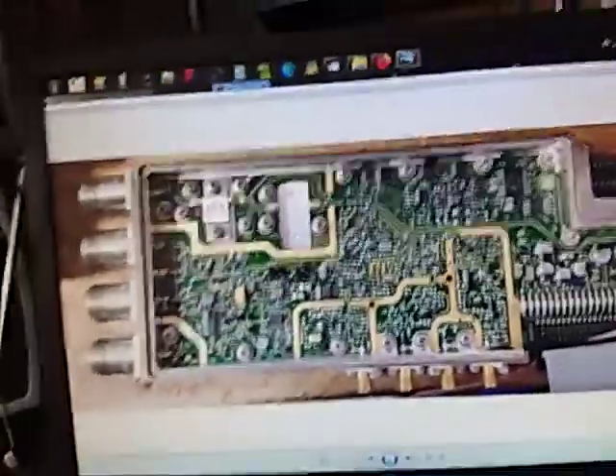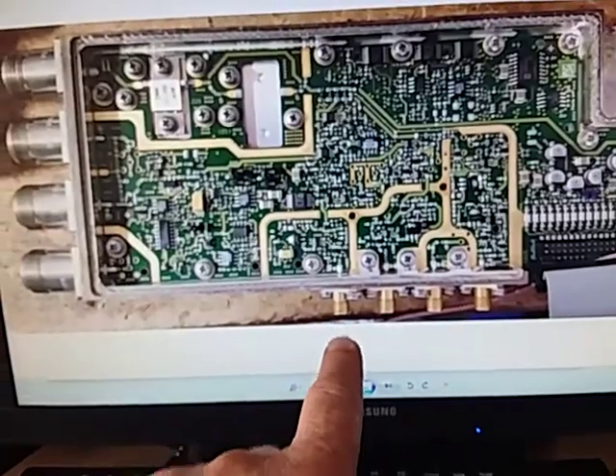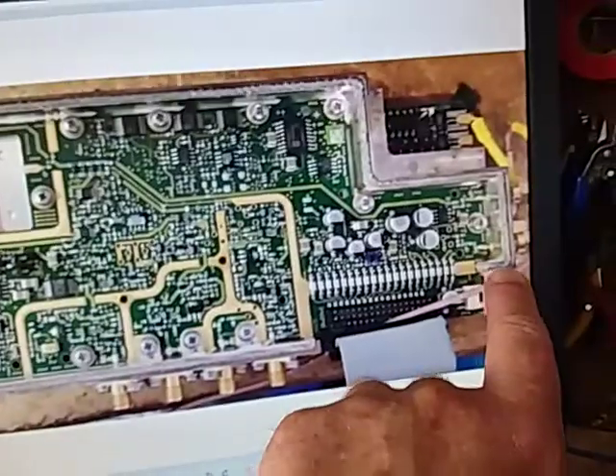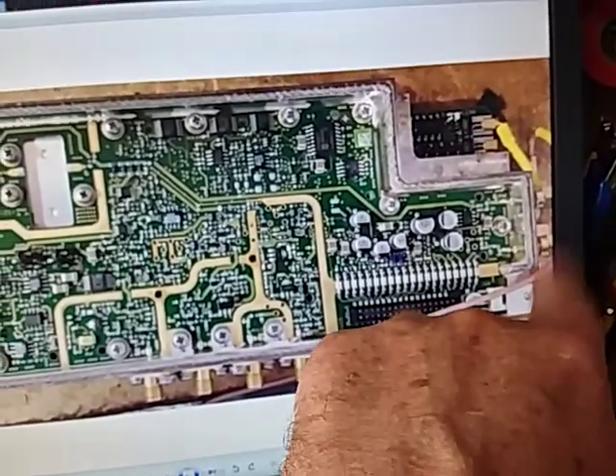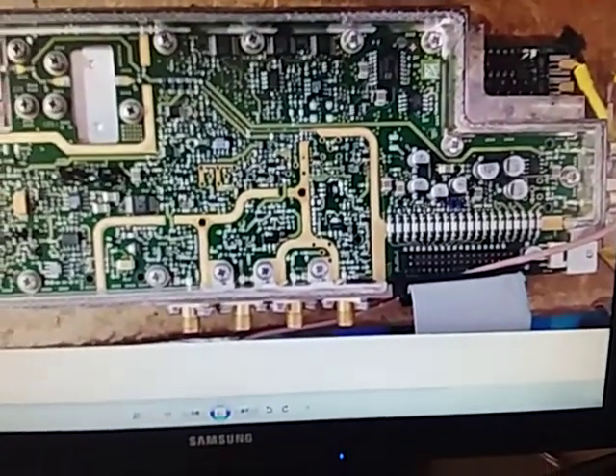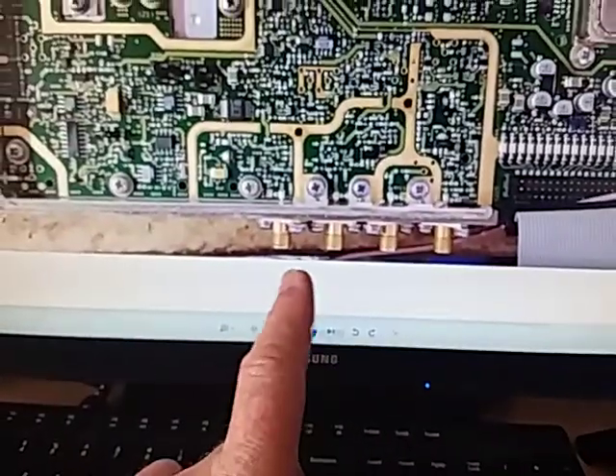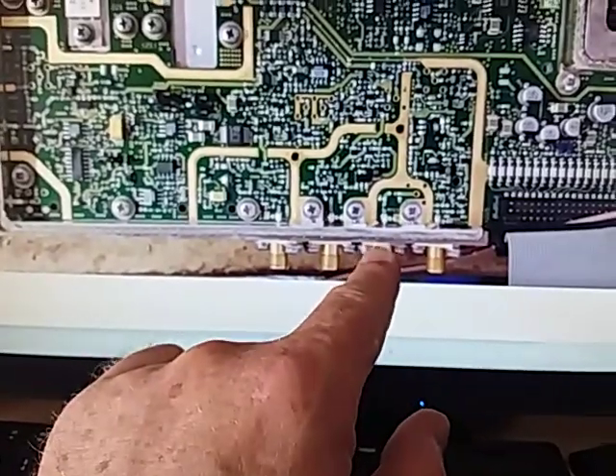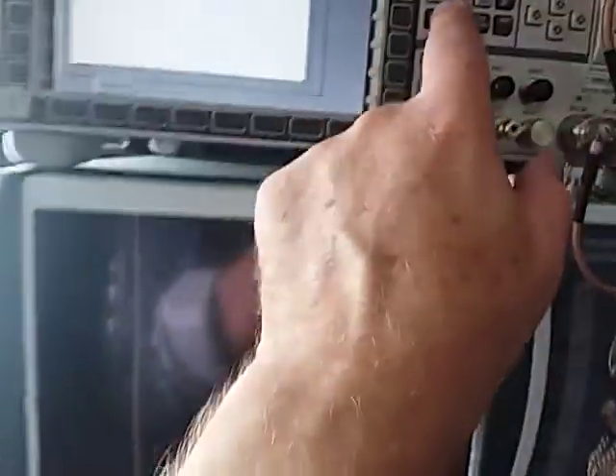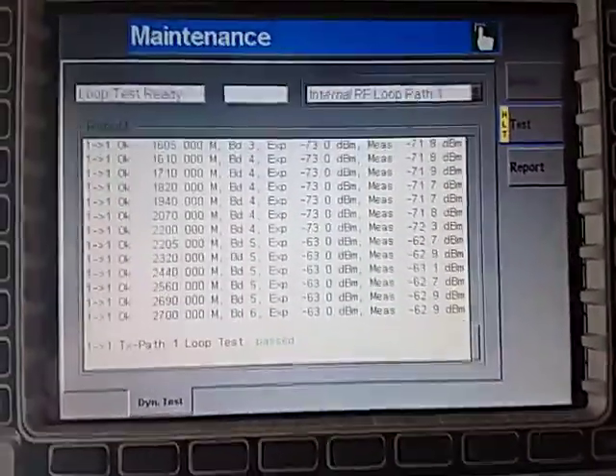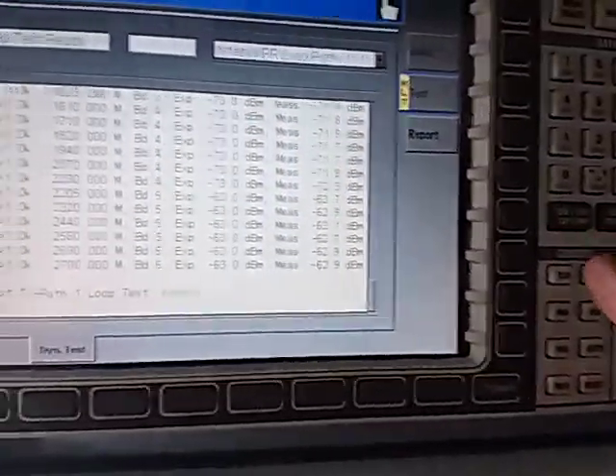Then we have the internal loopback paths, which is basically, this is the front end module, the RF loopback. The RF comes in and out via these ports and there's also some ports at the rear if you have the auxiliary generator analyzer installed as an option in yours. Some of them did have that. What this test is going to do is check to make sure that the loopback paths here, plus in the IF strip, are working okay. It's quite a quick test to run. You just press enter and it does the same sort of thing. It will test at every frequency.